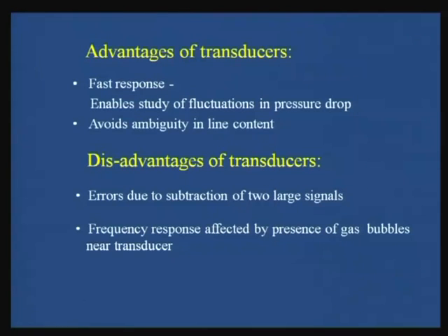Now, if this is a problem, then what will we do? Instead of subtracting the two signals, suppose we take the two signals to one device. With tapping lines, we connect the two signals to one device which has a diaphragm, and the two signals are connected to the two ends of the diaphragm. Then by the diaphragm movement, if you can measure the differential pressure, that will be more accurate. Instead of measuring each pressure and then subtracting them, this is definitely going to be more accurate.